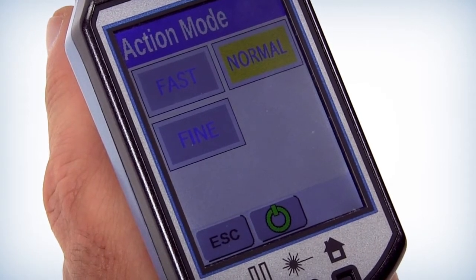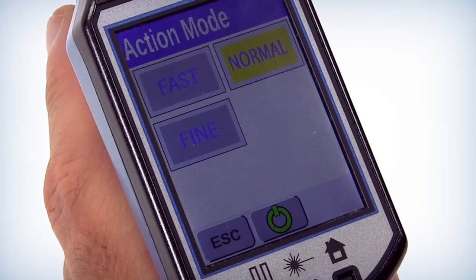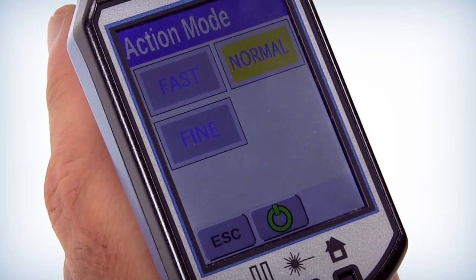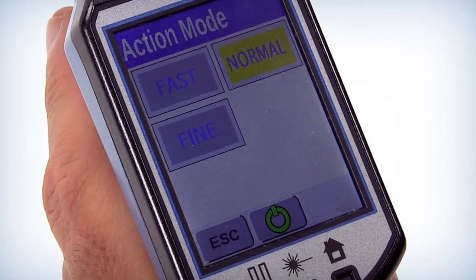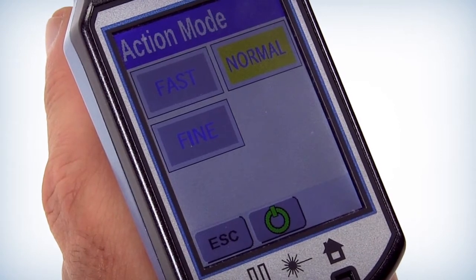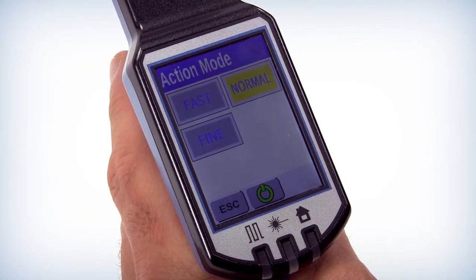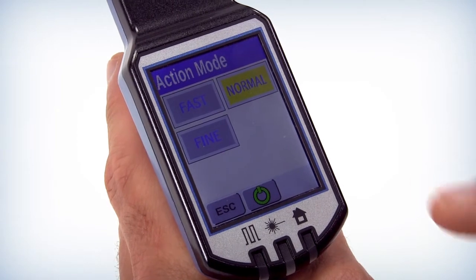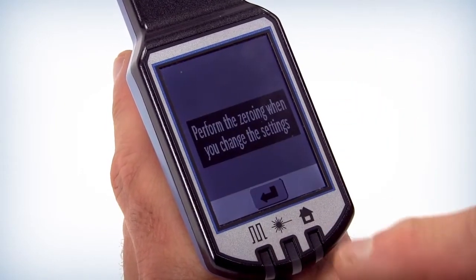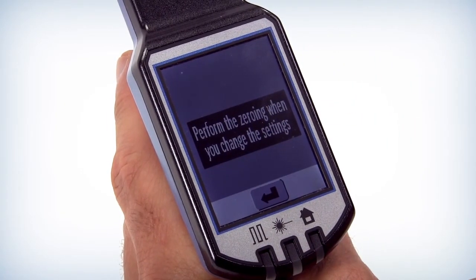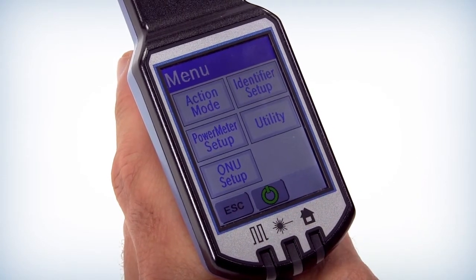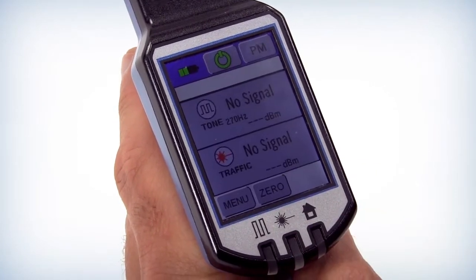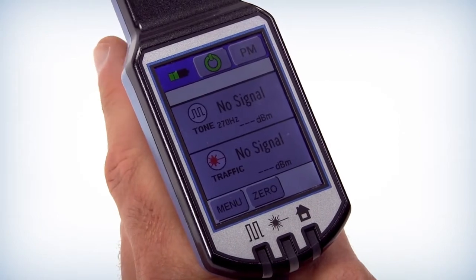There are three modes to choose from: Fast, Normal, and Fine. Fast is the fastest and most coarse while Fine is the slowest but most discerning. For most non-bend-insensitive fibers, Fast is sufficient. For more advanced bend-insensitive fiber, Fine is the appropriate setting. Exit the menu by selecting the Escape button in the lower left corner of the screen.